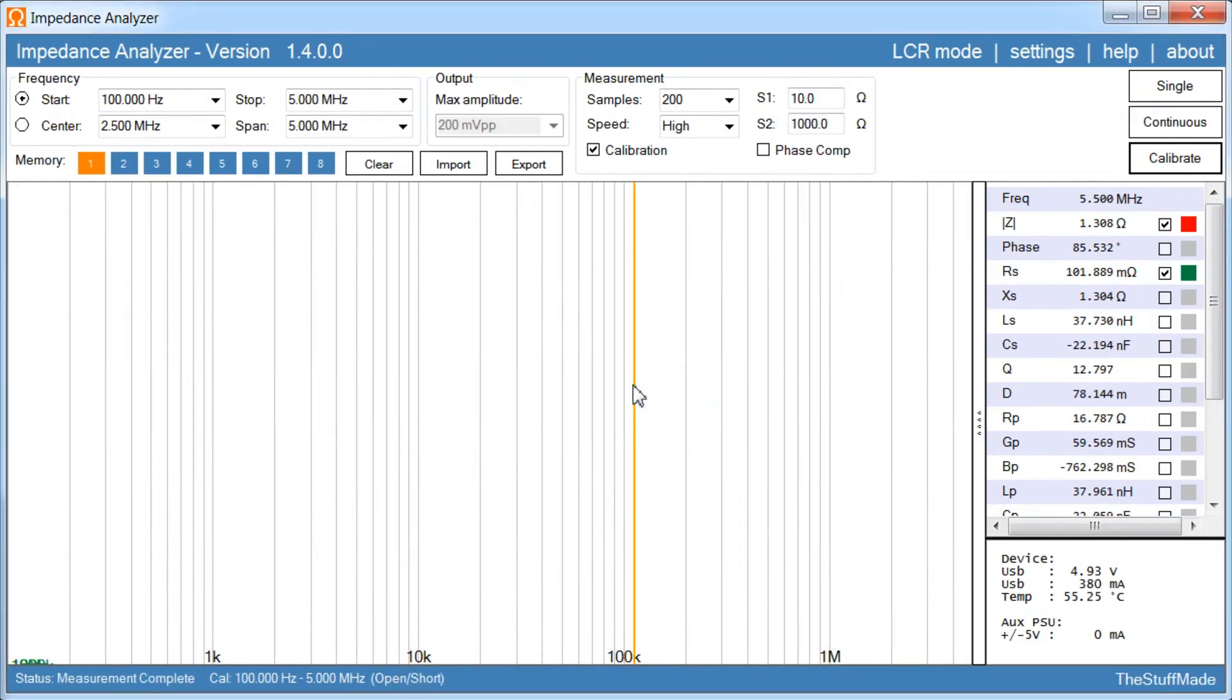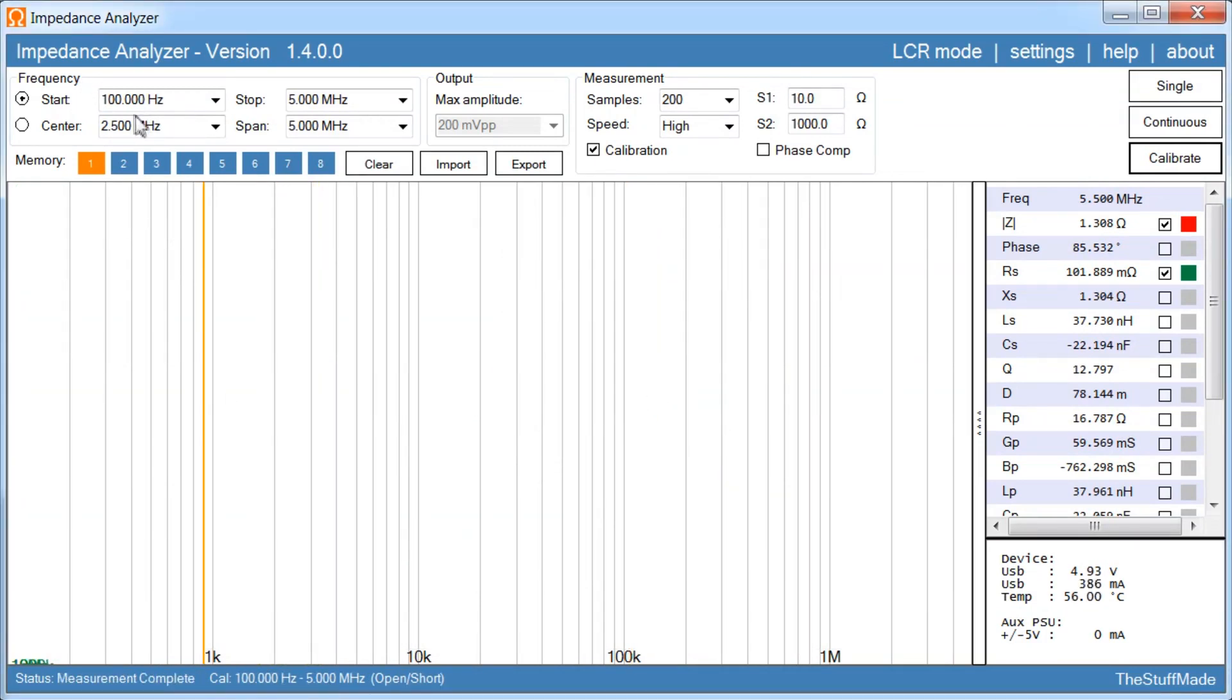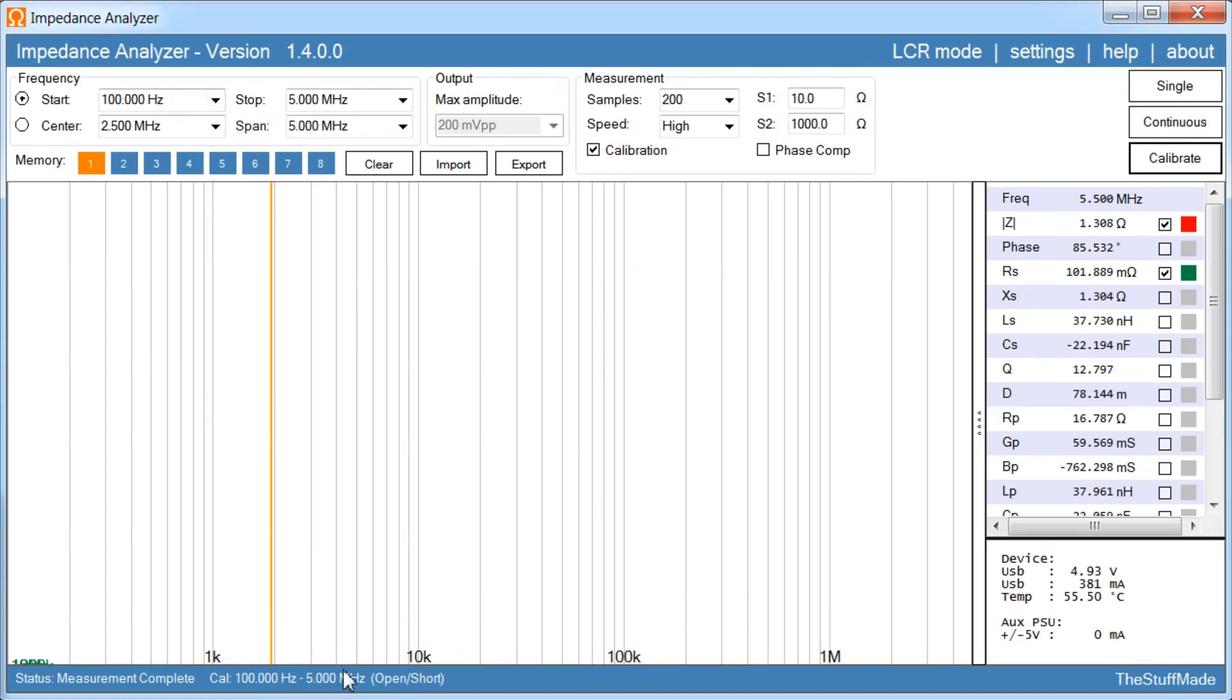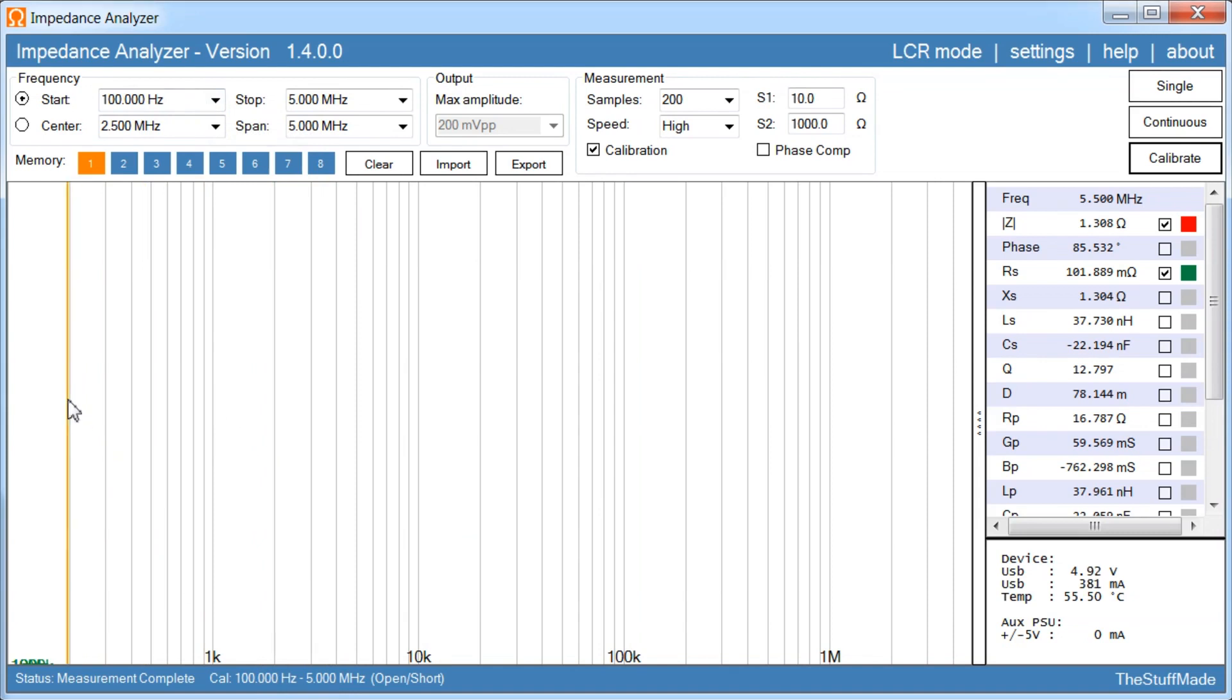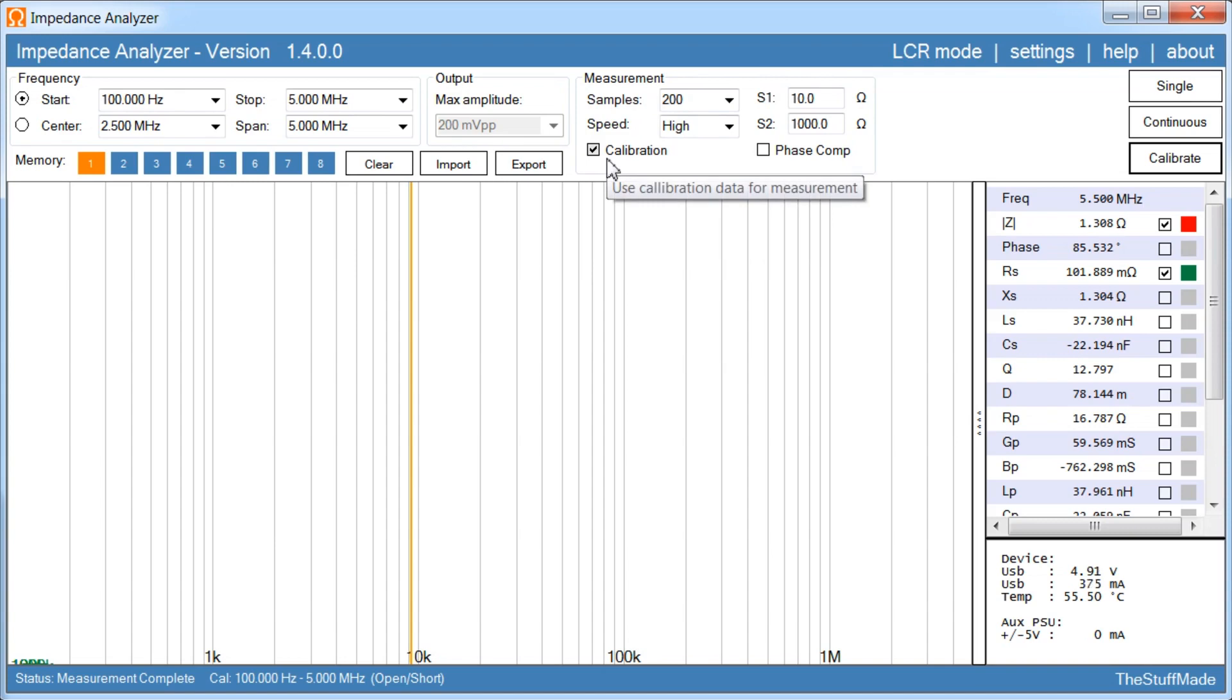So, one thing worth noting is that the calibrated frequency range is the same as the setting we have here, start stop frequency. And the number of samples during the calibration for each of the shunts is the same as the value we set up here. So now we have calibration, let's try to do a measurement.